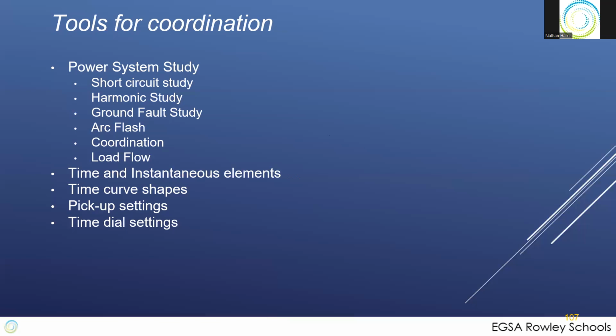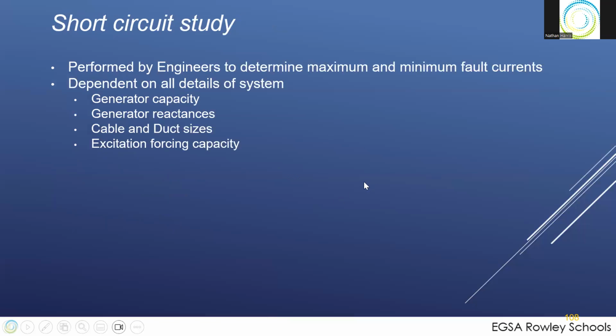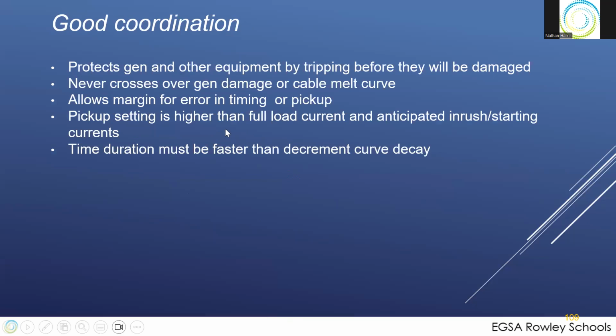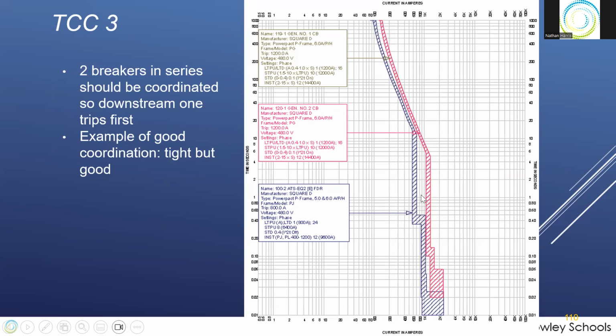Somebody needs to be doing this short circuits, this power system study, of which part of it is the short circuit study, to determine all these different factors, cable size, duct type, it's a plastic conduit versus an EMT or rigid, all make a difference on that. And you want to end up with good coordination where you don't cross each other and yet you provide as much protection as possible. And here is another time current curve of a well-coordinated system, very tight, but good coordination between a 1200 amp breaker and 800 amp breaker. It's like there's two 1200s and an 800 amp breaker.